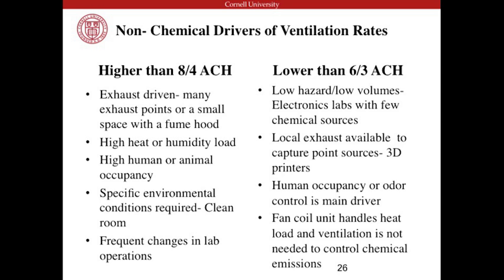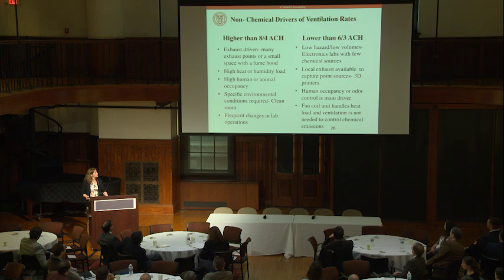And then the labs that fall below the 6 and 3 air exchanges—they're very low hazard, with very small quantities of chemicals, so chemistry isn't really driving the ventilation rates. There are local exhaust points that actually capture the point sources.